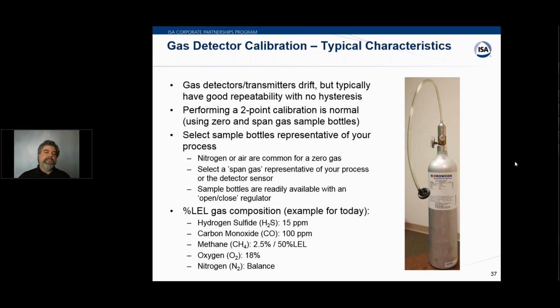So if you have an oxygen sensor and you've got nothing on it, you're going to read 21%, or you should. So that's why sometimes we'll take a bottle of nitrogen and shoot that at the sensor to give us a 0 on the oxygen. So make sure you pick a proper source or proper bottle to do what you're doing. So nitrogen is common for 0 gas or air.